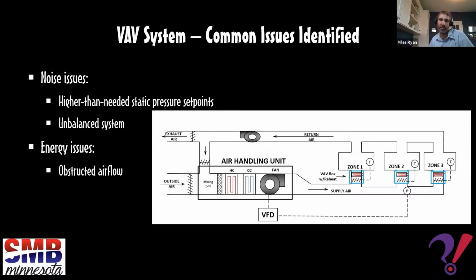Other issues that might occur would be energy issues. So I previously was talking about this high-rise residential project we're working on right now, where the TAB contractor didn't come in until December, even though the system was up and running since the previous May. Well, when they came in, what they found is in one of the main ducts of the system, it was an existing duct that they reutilized. And what they found is that there was internal insulation lining inside that duct. Some of it had broken away, flipped up, and was basically creating a huge blockage in the system.